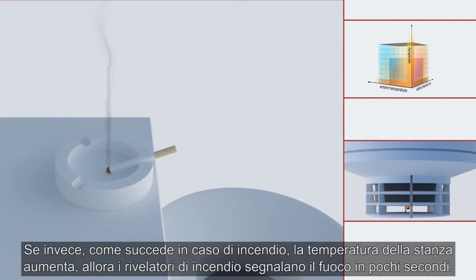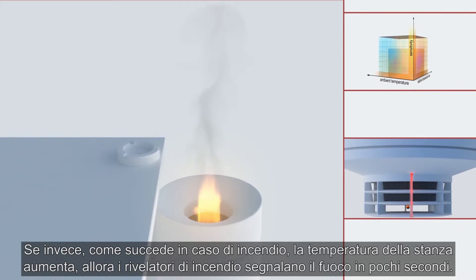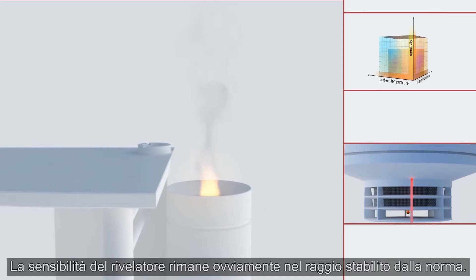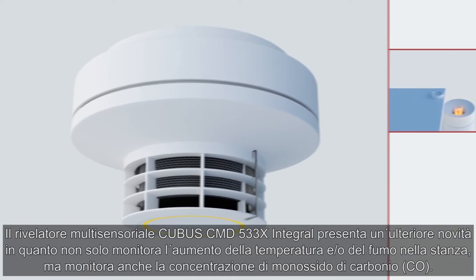Thanks to Cubis leveling, the CUBUS CMD533X simply filters out cigarette smoke or dust. If, however, in the event of a fire, the room temperature increases, then the fire detectors automatically become more sensitive and detect a fire in seconds. The sensitivity of the detector, of course, always remains within the range set out in standards. The Integral Cubis CMD533X multiple sensor detector is another new development.